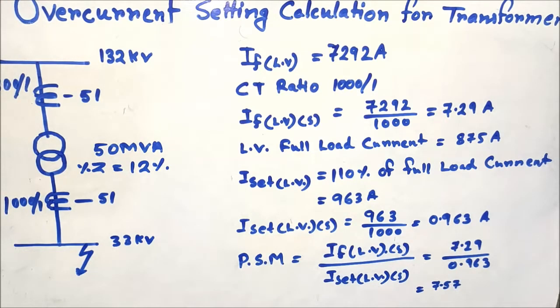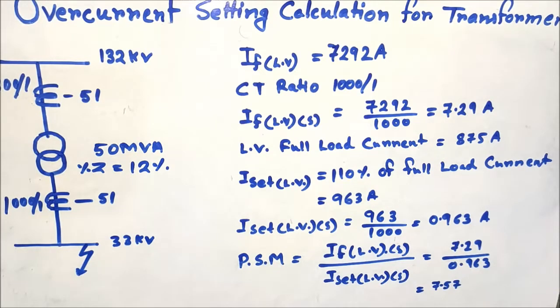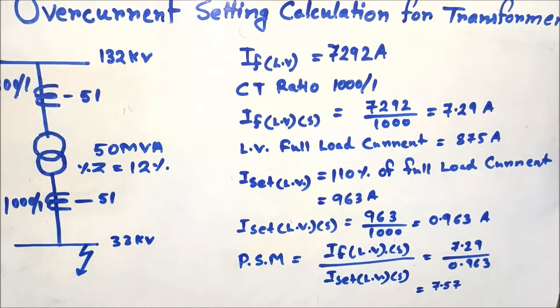The current set value for the LV overcurrent relay is 110% of the full load current. The full load current is 875 amperes, so 110% gives 963 amperes. Reflecting this to the relay secondary by dividing by the CT ratio of 1000/1, the I_set on the secondary side is 963 divided by 1000, which equals 0.963 amperes.